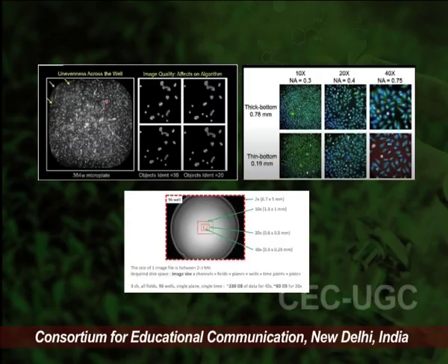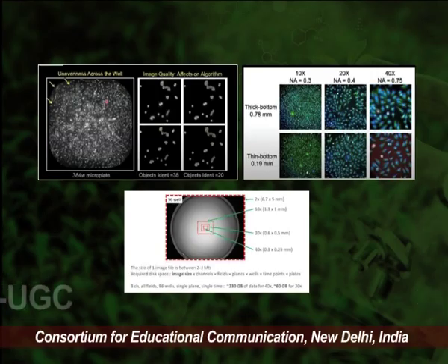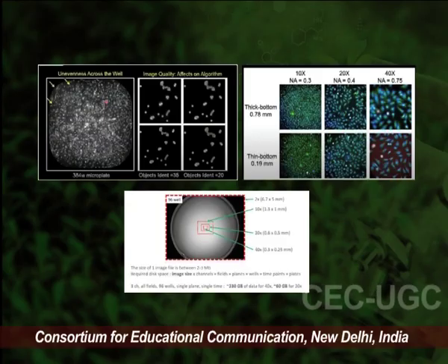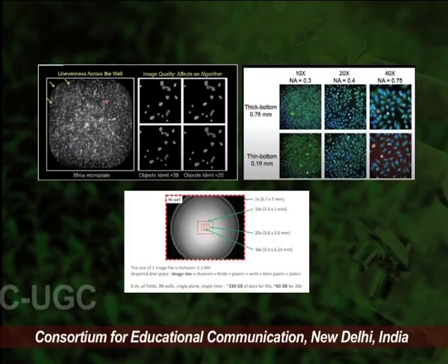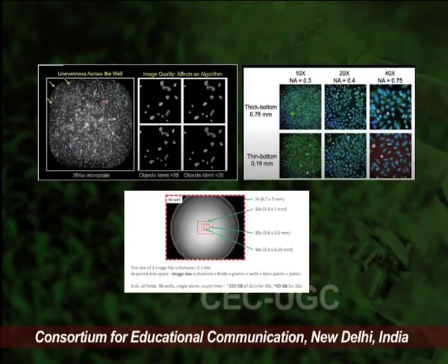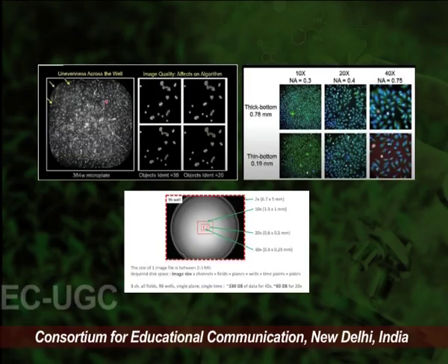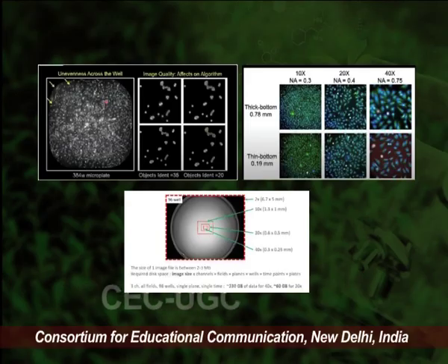So these were a few examples of why the selection of the microplate is very critical. We have to be very careful. The wall should have uniform thickness, the base should have appropriate thickness. If you are using a flat base, no issues in clicking the image, but if you are using curved base microplates, then it is always preferred to click the image from the central region of the plate, because again the thickness will vary in the curved region.